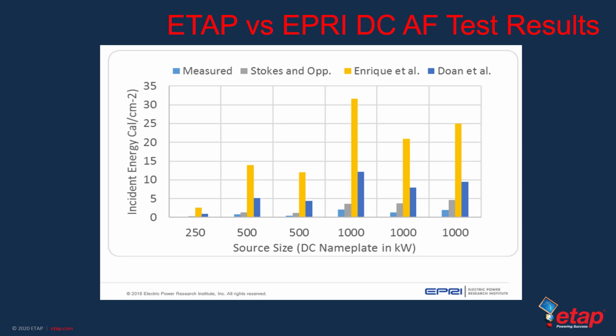For the 1 megawatt photovoltaic array that they used to test, the measured results were in the range of 2.5 calories per centimeter square. And the Stokes and Oppenlander results, using the double iterated method that we have available in ETAP software, produce about 3.5 calories per centimeter square. The remaining methods, as published in the references that I showed earlier, are off by 6 to 10 times, as can be seen in this slide.